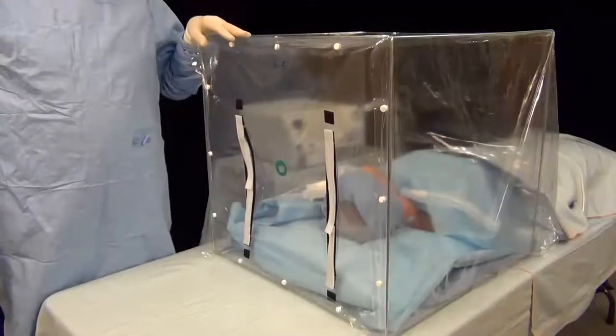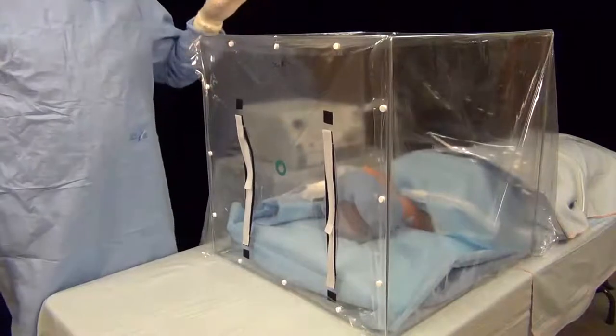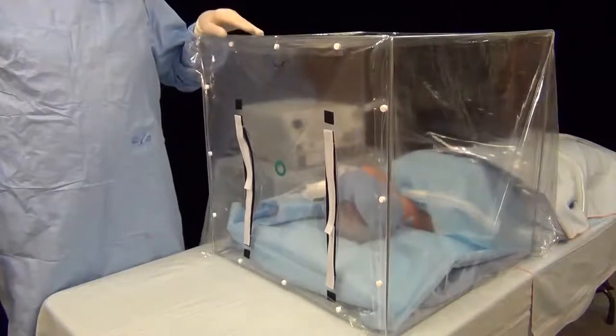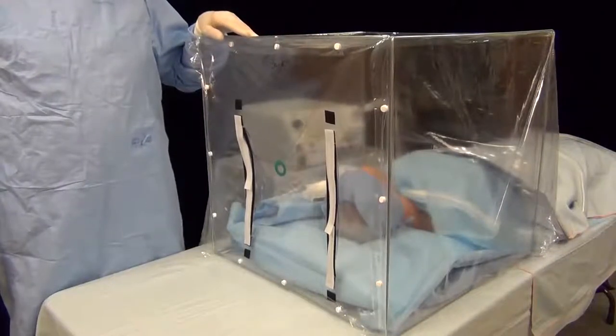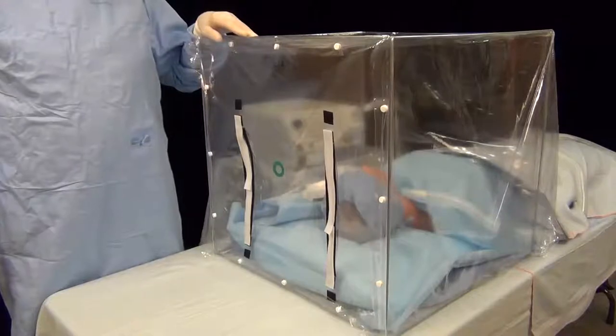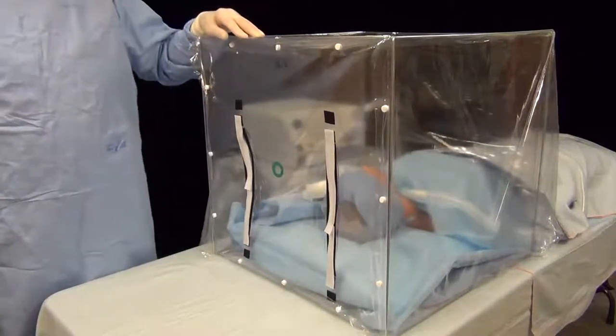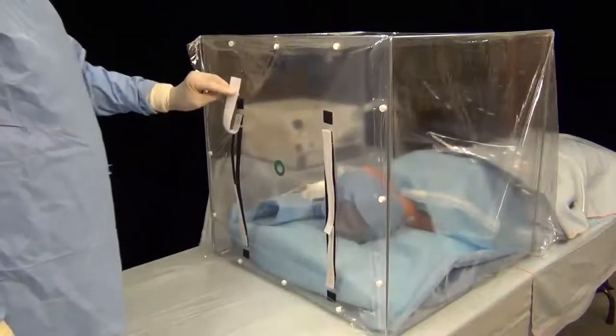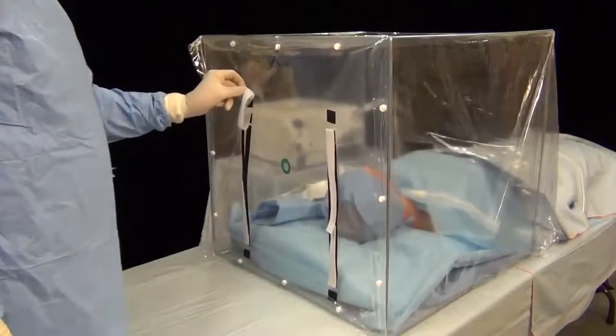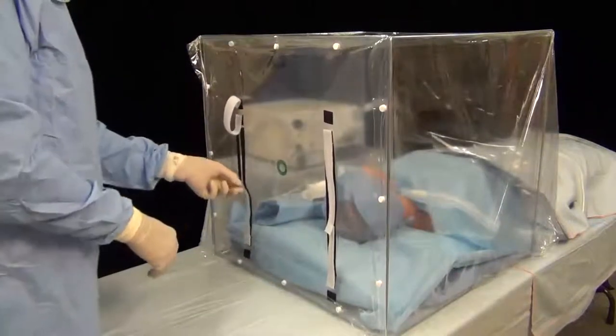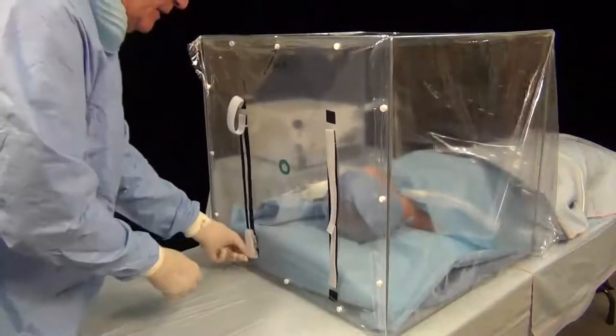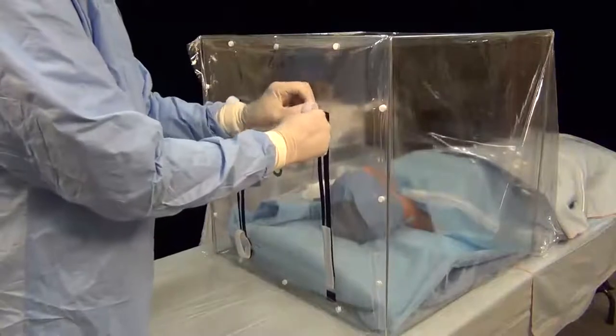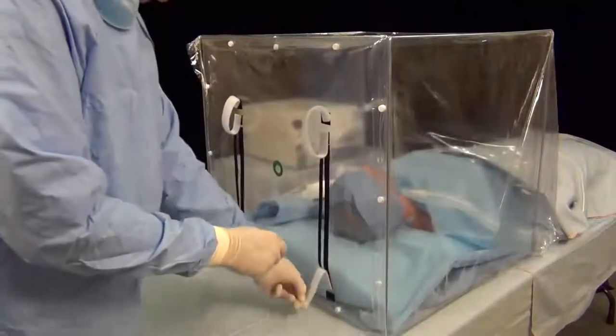Now that the tent has been constructed, the patient is in place. The respiratory tubing is already inside the tent, ready to be connected to the endotracheal tube. Now let's see how we can access the patient for purposes of intubation or extubation. First thing we should do is pull up the tabs that expose the opening. These are held in place by these tabs just beyond the access port, so they stay out of your way.